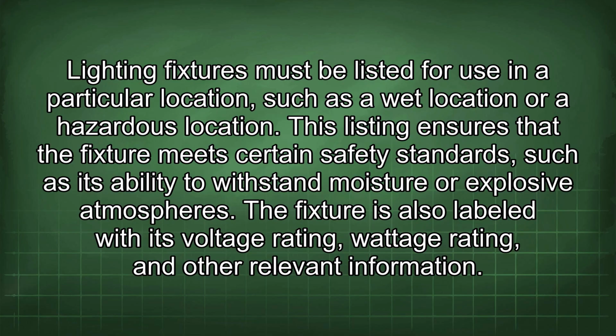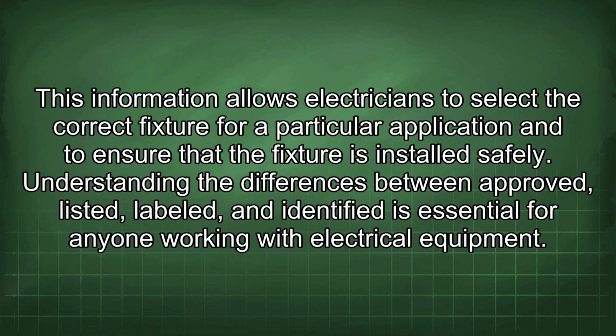Lighting fixtures must be listed for use in a particular location, such as a wet location or a hazardous location. This listing ensures that the fixture meets certain safety standards, such as its ability to withstand moisture or explosive atmospheres. The fixture is also labeled with its voltage rating, wattage rating, and other relevant information. This information allows electricians to select the correct fixture for a particular application and to ensure that the fixture is installed safely. Understanding the differences between approved, listed, labeled, and identified is essential for anyone working with electrical equipment.